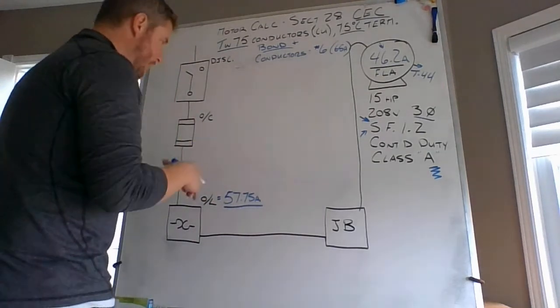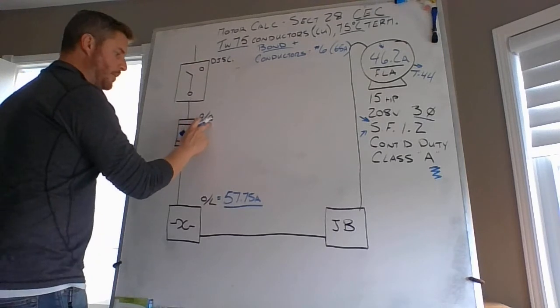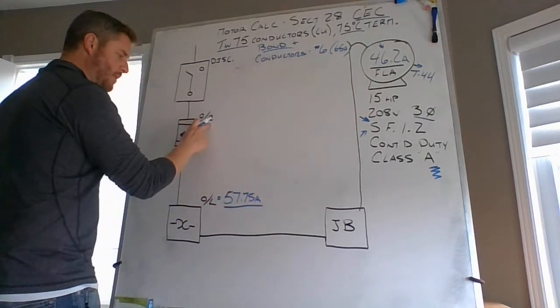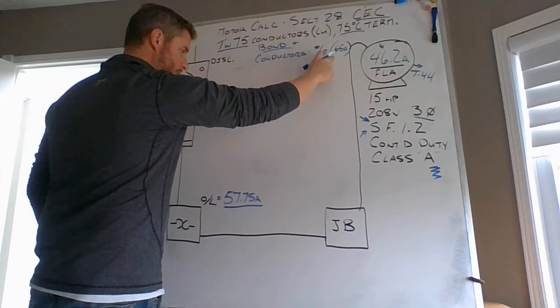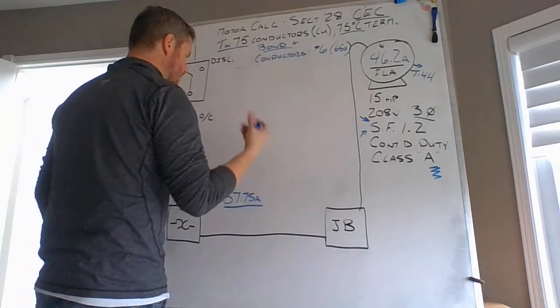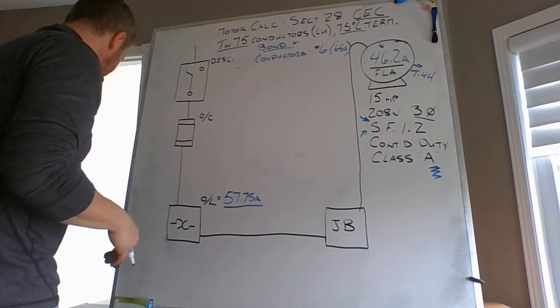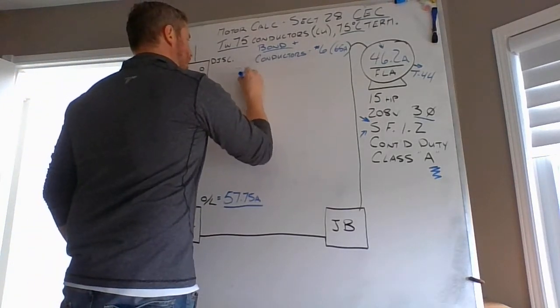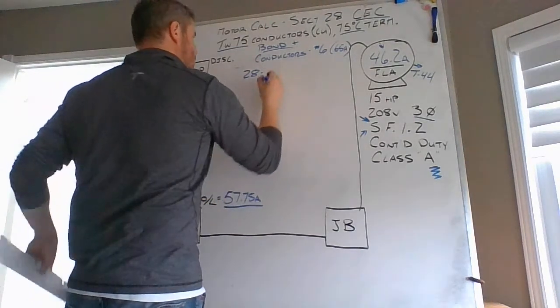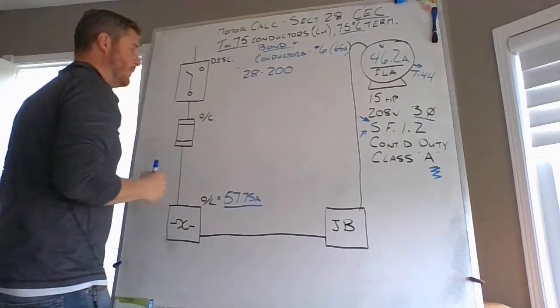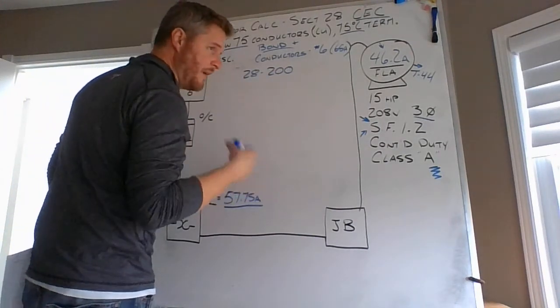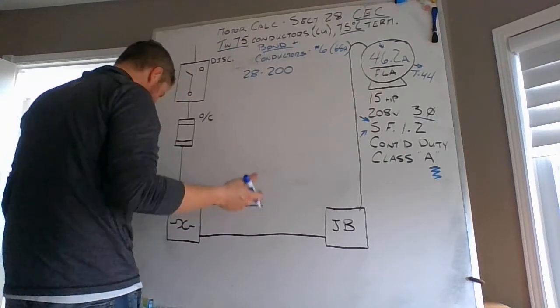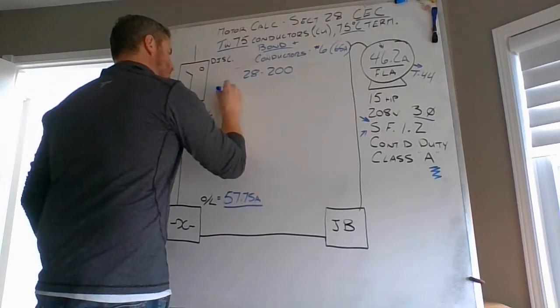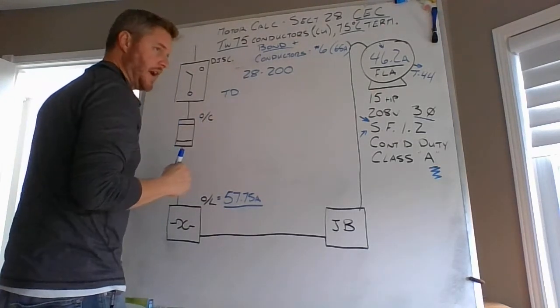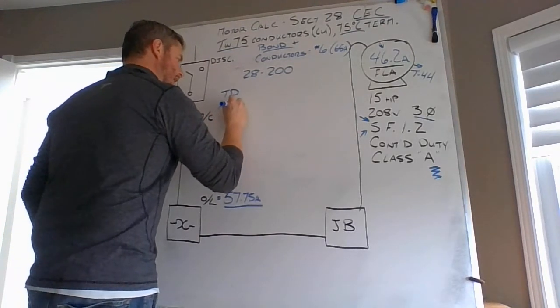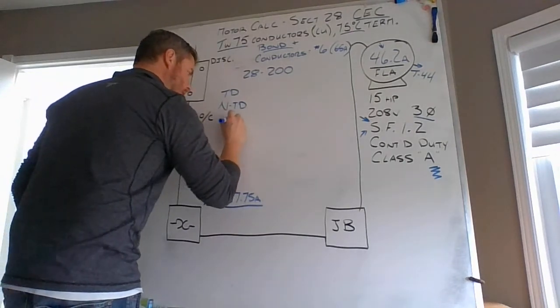So anyways, we have a few different options when we start into consideration for our overcurrent protection. And here is where you will figure out that your overcurrent protection does not protect your conductors. It does not. And I'll show you exactly how it doesn't in just a minute. When we go through and we look at overcurrent protection, we're concerned with 28200. 28200 tells us that we realistically have 3 different types of most commonly used overcurrent protections. And those are time delay fuses, TD representing time delay fuses. We also have non-time delay fuses. And we also utilize circuit breakers.